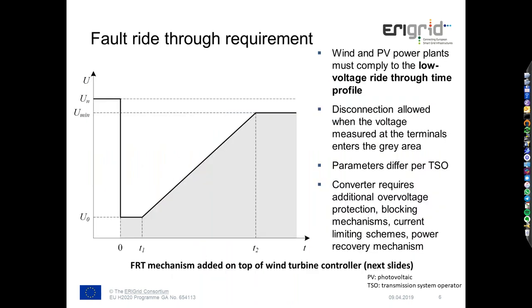what we understand under fault ride through and how we implemented the vector controller. Fault ride through is one of the regulations that power plant owners have to comply to at the coupling point, the point of common coupling. It's commonly described as a voltage versus time profile: if the voltage at the point of common coupling remains above the envelope shown here, the wind turbine has to remain connected during a fault. If it enters this gray area, the envelope, then it either must block its active power output or disconnect.